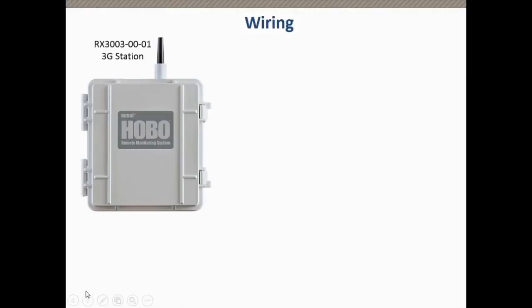Inside the room, you can see here there's a sprinkler configuration. This is a wet pipe type sprinkler setup, and we're going to be monitoring the temperature in here as well as the relative humidity, and we're going to monitor the AC voltage so we can get notified if the power goes out. The wiring configuration of this hardware is as follows. We used an RX3000, which is the 3G station. We wanted to use something that was independent of the building infrastructure in case the power went out. So this device is a standalone. It has that 3G modem in it, and it will be able to communicate even if the power goes out and send us our alarms.